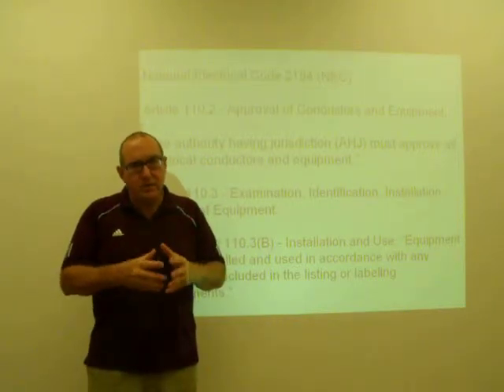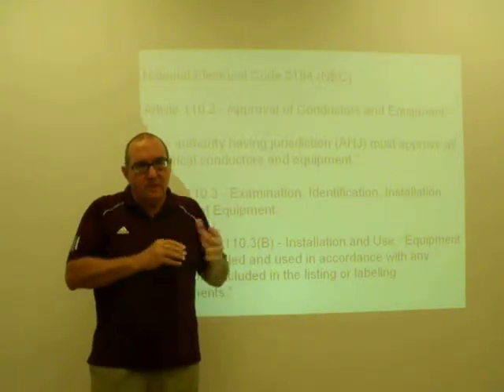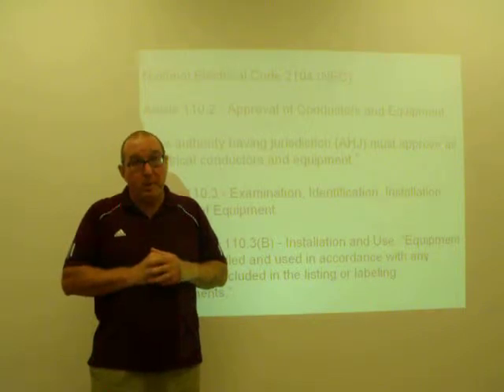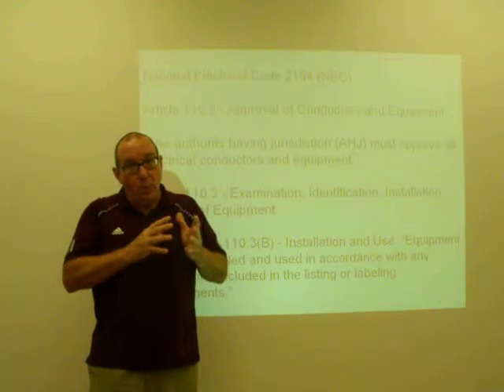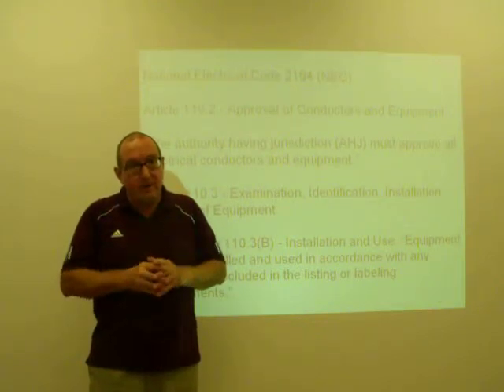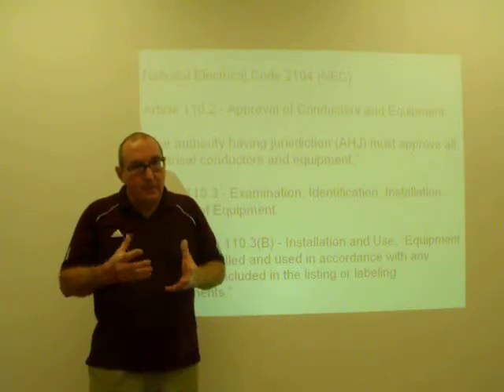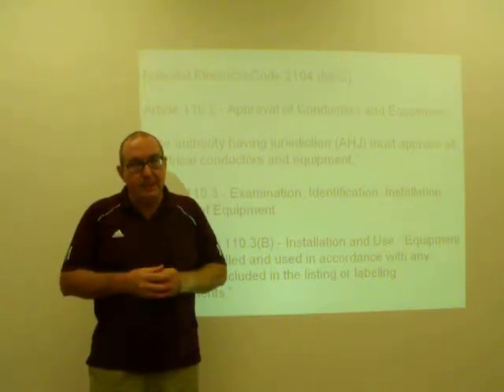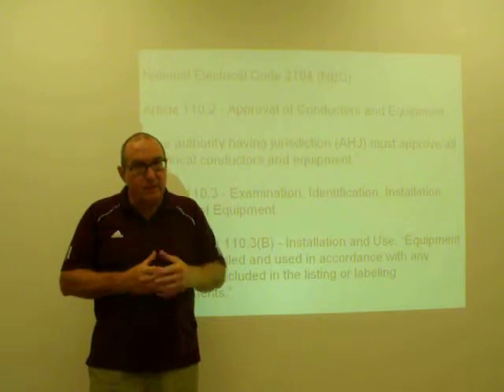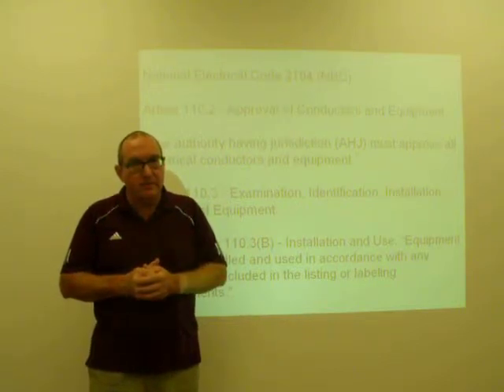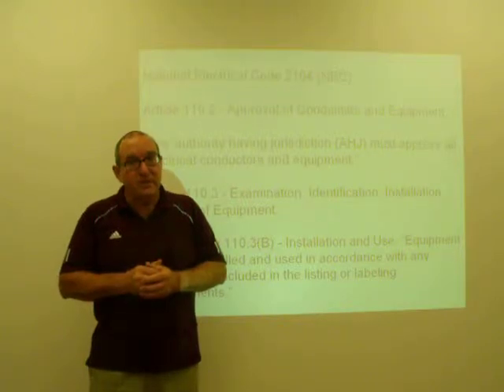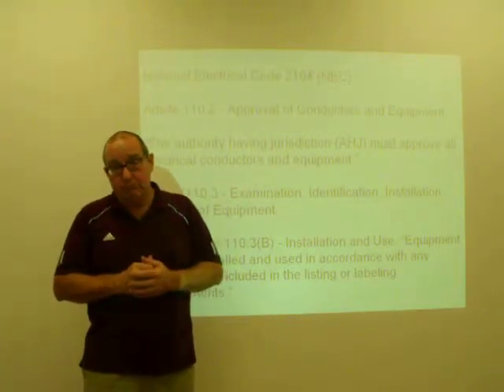There are some different arguments around about what we call classified breakers and whether they really comply with this paragraph. However, one of the other paragraphs I haven't quoted here says that if something is listed or labeled by an appropriate agency, then it may be legal for use. And in all cases, classified breakers are UL listed for their application, even though some panel board manufacturers may insist that you can't use them in their panel.